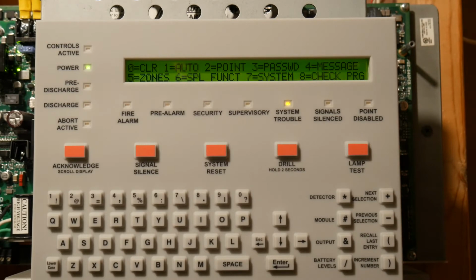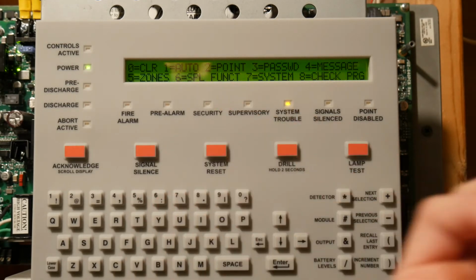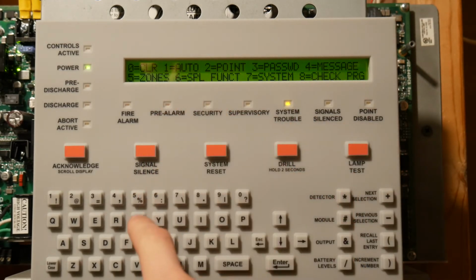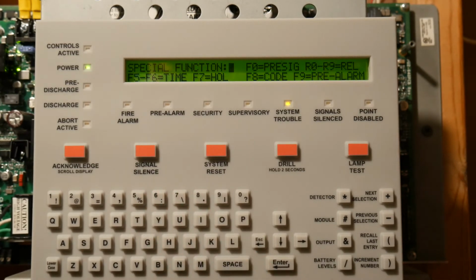Okay, now I'm going to go into special functions. Special functions is number 6, so we're going to press 6. Special functions are basically how you set NAC coding, releasing, like agent release time. You can set your coding options, your pre-alarm, all that.